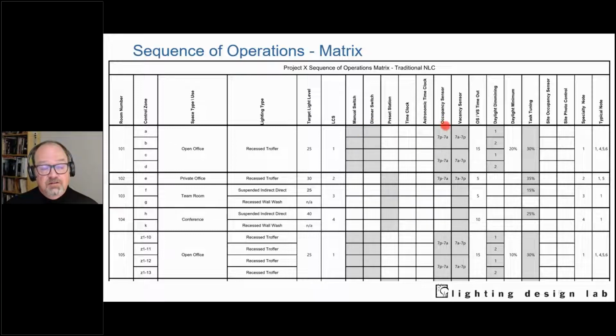It's set up, and this is a little tricky, from 7 p.m. to 7 a.m. the sensors are occupancy sensors; from 7 a.m. to 7 p.m. they're vacancy sensors. Why? I like vacancy sensors, and I like occupancy sensors too, but the reality is during daytime hours a vacancy sensor works pretty well, while at night an occupancy sensor tends to work better. Why? Because if the lights false-trigger off at night, you don't have any other light, so you stumble over to the switch to turn it back on. Whereas if it false triggers off, which is relatively rare these days, you can just wave around and get it to turn back on. During the daytime it doesn't matter much because you're likely to have other light sources in that space.